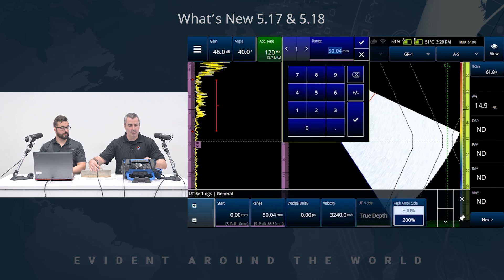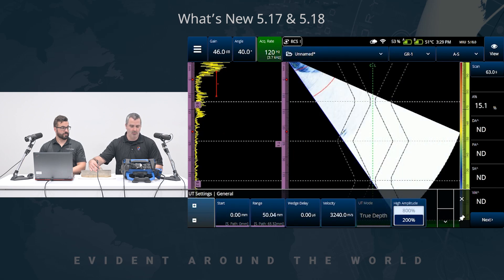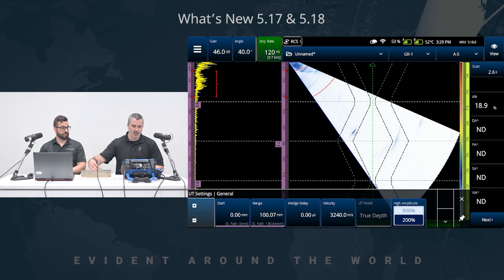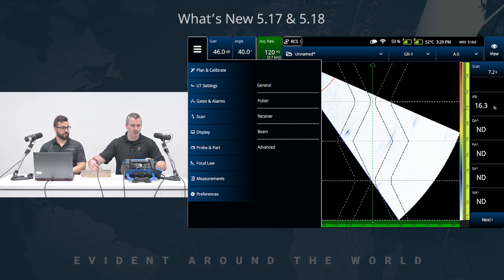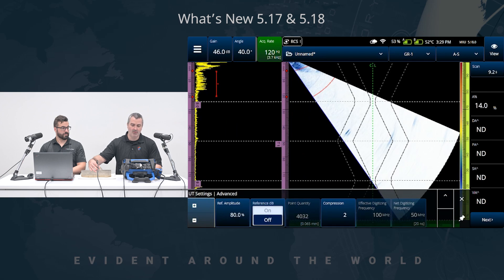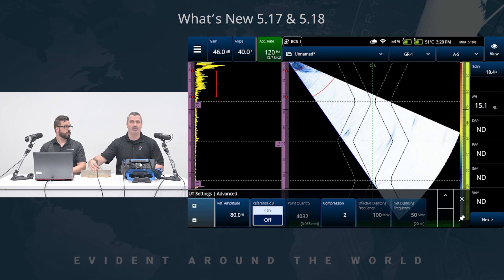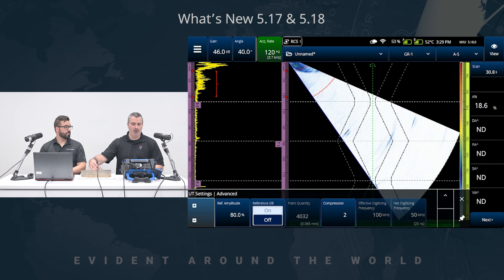Go to General, type in the new range. Now we have plenty to cover the first leg, the second leg, as well as the side drill holes for calibration. But now, if I return to advanced, we still have a compression factor of 2, meaning still a net digitizing frequency of 50 megahertz, to respect the procedure guidelines or inspection codes. But the point quantity is now adjusted — it's no longer linked to range adjustment. You have full control over the essential variables.